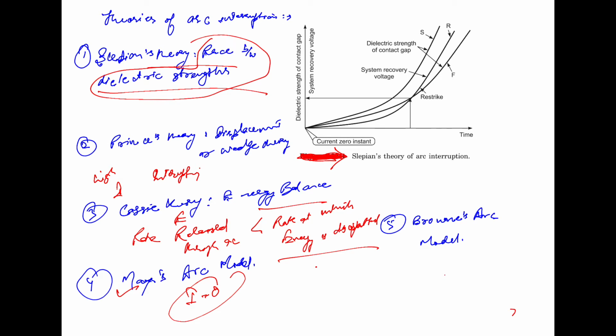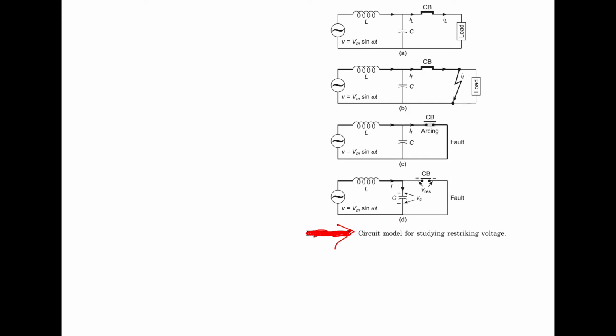Now, next is the restriking and recovery voltage. So what is restriking and what is the recovery voltage? Restriking and recovery voltage play a very crucial part in the operation of the circuit breaker. The voltages are intimately related with the parameters of the power system and the phase angle of the current being interrupted. We will assume in this lecture that the circuit breaker is ideal. The current is interrupted at the current zero, and there is no premature extinction of the arc. So we assume the circuit breaker itself does not in any way alter the recovery voltage.